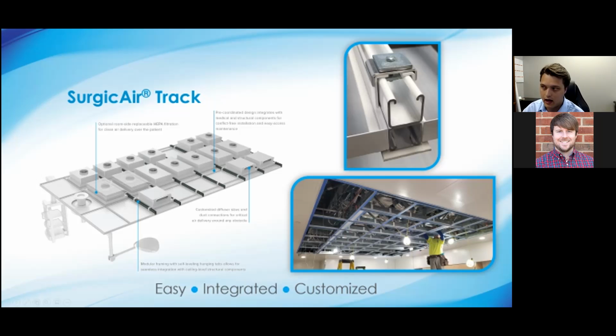When the imaging equipment vendor comes to install their equipment, their blocks need to slide freely in that bottom channel to mount the imaging equipment. If you have screw tips poking into it, they might have to burn a whole day chiseling off those tips just to get their equipment in. A design delay that causes an imaging equipment vendor to reschedule usually costs another 3 months before they can get back out to finish the job.